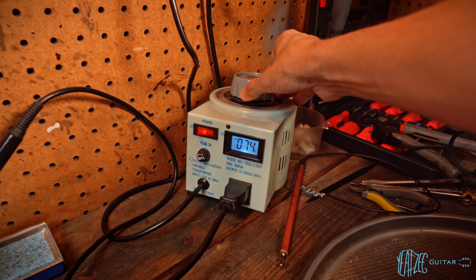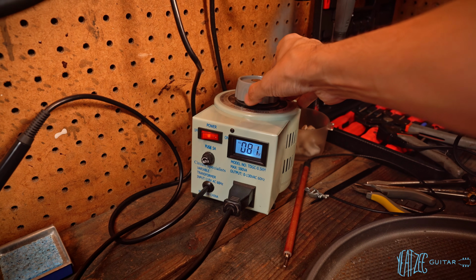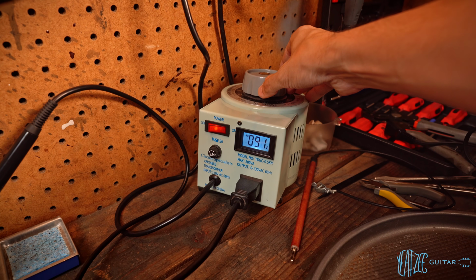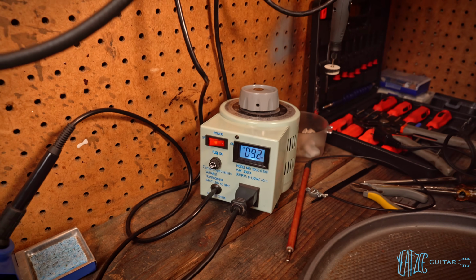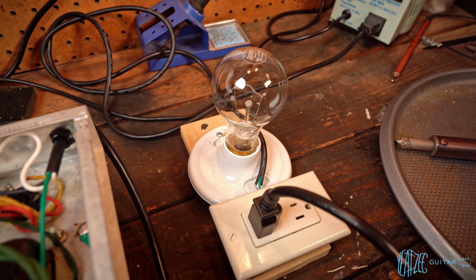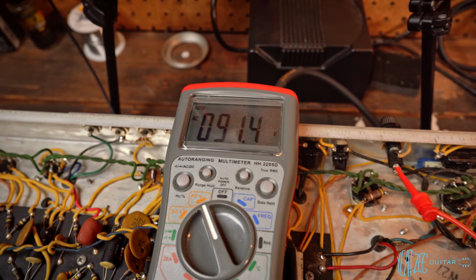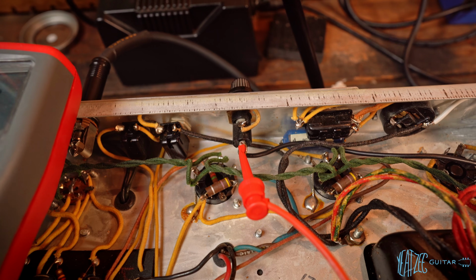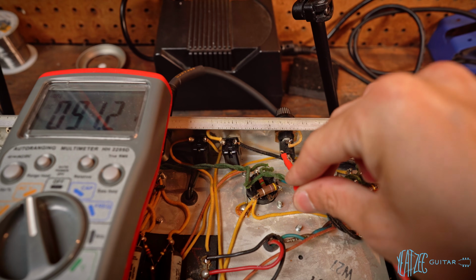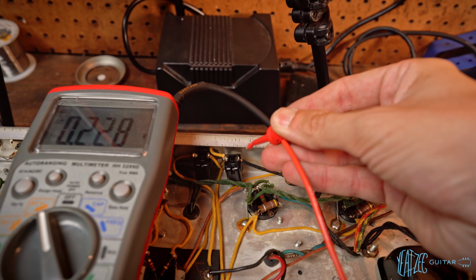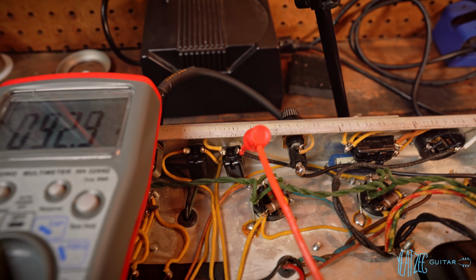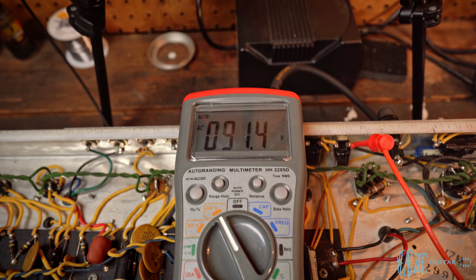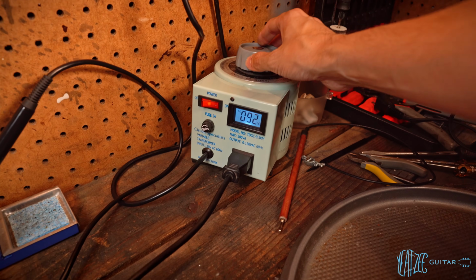Continue to slowly bring that up. Now we're at 91 volts or so. The light bulb is not lit up, which is good; if it lights up, that means something is wrong. We are getting 91 volts right here to the tip of the fuse. Just to check real quick, we'll pull this off and connect it to this part of the switch, which should be getting the same, and it is.